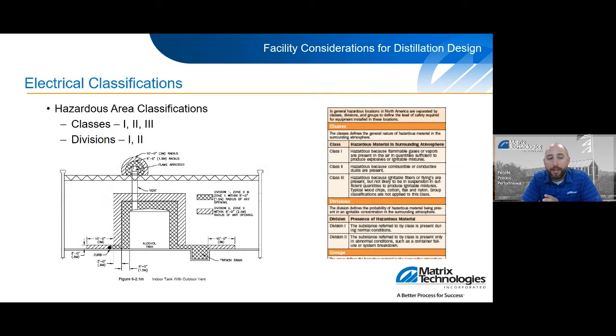So electrical classifications really revolve around the hazardous areas that you define as part of your code review. Typically, we're working with the H groups, as I mentioned in the last slide, which are your hazardous groups. With alcohol handling, we're in the Class 1 Div 1 or Class 1 Div 2 realm, where Class 1 means vapors are present in the areas in large enough quantities to cause an event. And then the Div 1 is they're present under normal operating conditions. And Div 2 is really present in abnormal scenarios. So for example, that would be your grain handling or a tank failure or a system breakdown that is not anticipated, but it could happen.